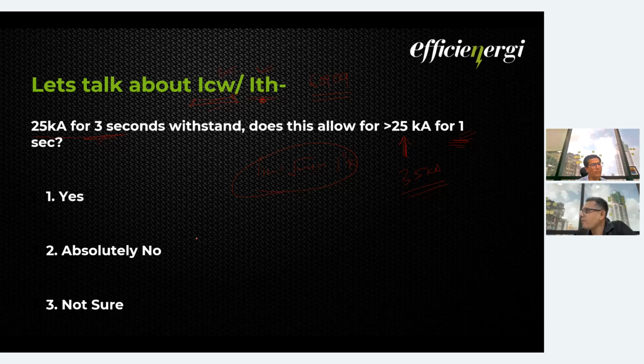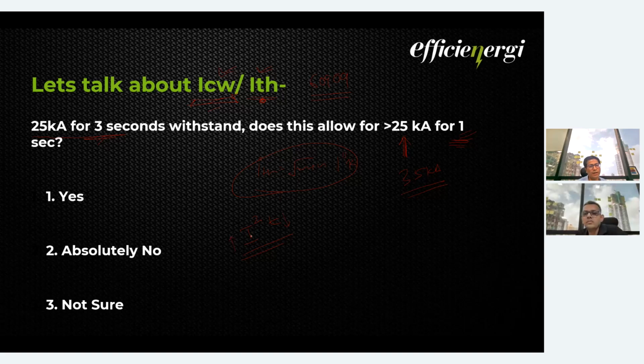Okay, so almost 50% say yes. You can. Basically yes, because this completely depends on the I square T value. So it is inversely proportional: the lesser the T, the higher the ampere we can go for. But if you see the IEC standard or IEC testing, the manufacturer will give 3 to 4 different figures for this. It is not completely blindly based on the I square T value.